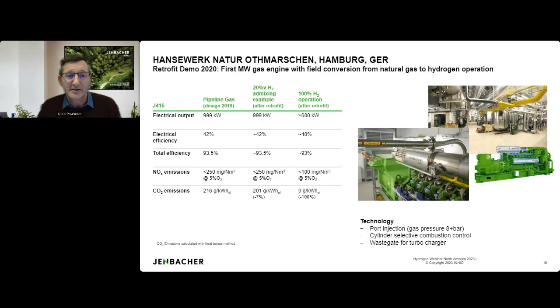This project is from 2020, where we demonstrated a first field conversion from natural gas to hydrogen operation in Germany. It was done in Hamburg at the customer site, where we installed a 1 megawatt CHP engine with very high total efficiency, over 93%. This engine was converted in the field from natural gas to 100% hydrogen operation.